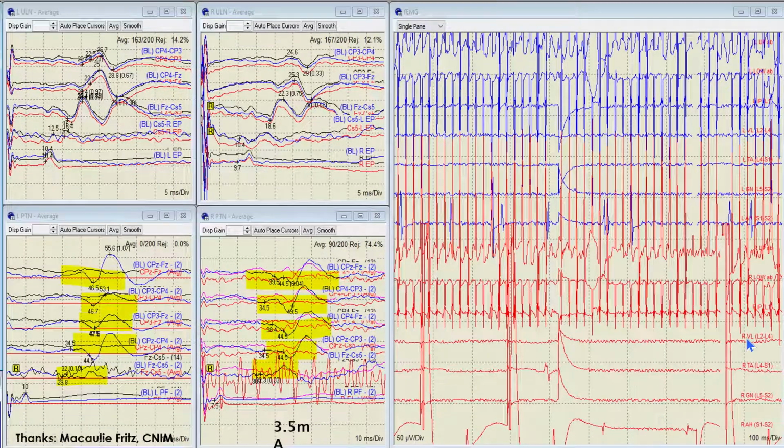This is what one might look like. We do EMG over here, and we do the SSEPs over here. You can see the blue is the baseline, beautiful baselines there. We turn the stimulator on. That's what all this noise is, the stimulator turning on. So it validates that it is on. And you can see the red here on this side and the black here on this side. It just, boom, those responses go away.